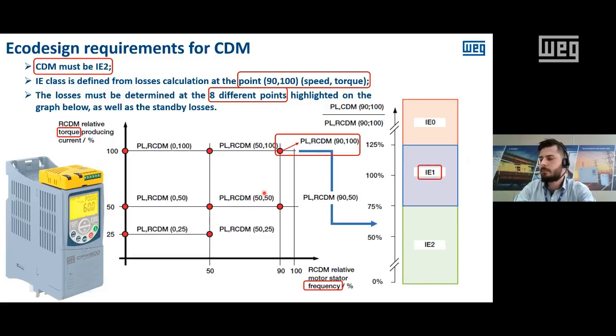Okay, so if you look at the regulation, there will be tables defining the values of losses, and these losses were defined for a reference complete drive module, the RCDM. And these losses were named IE1. So if you have reference values of IE1 and you need to be IE2, the standard says that you should have at least 25% lower losses than IE1. Then you're going to be IE2. So IE2 is going to be lower than 75% of the losses of IE1.